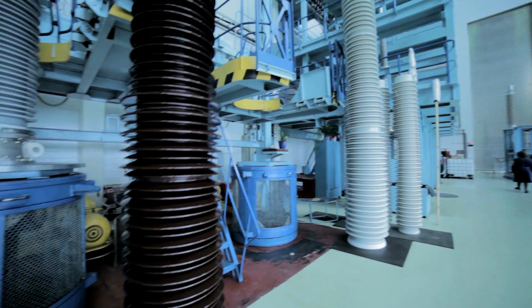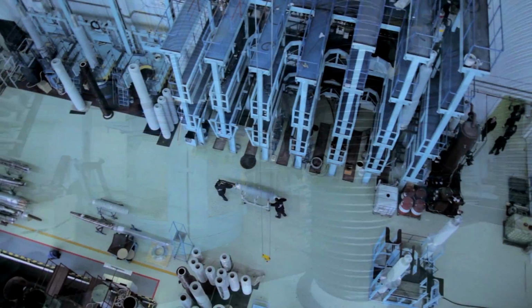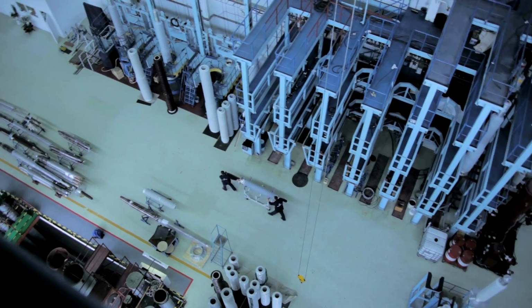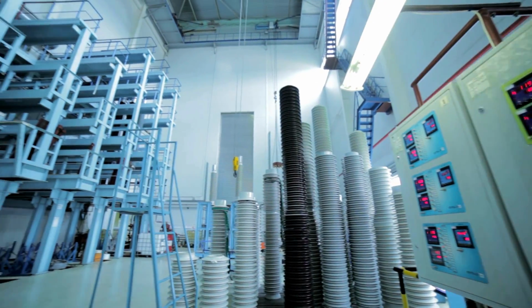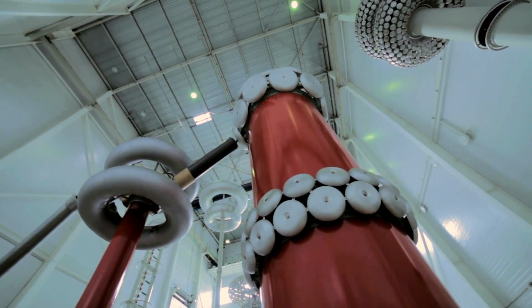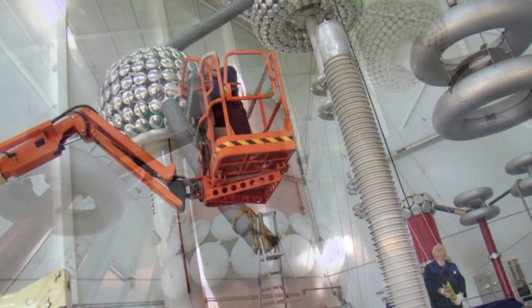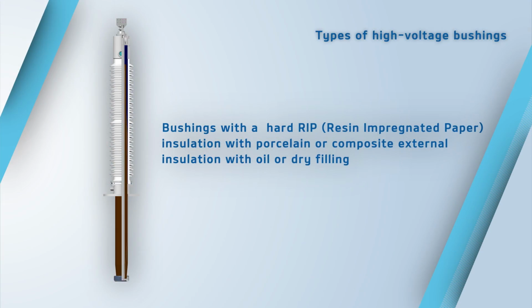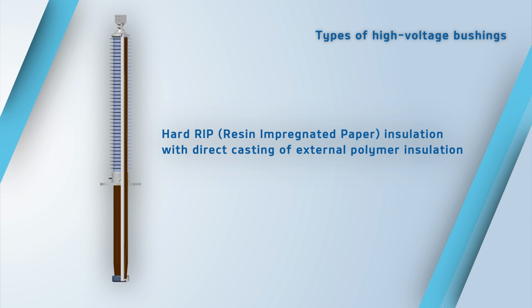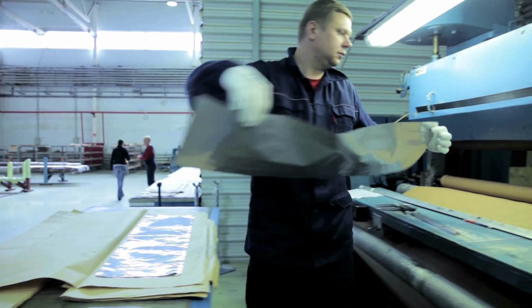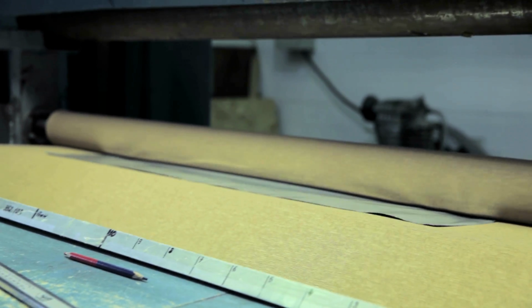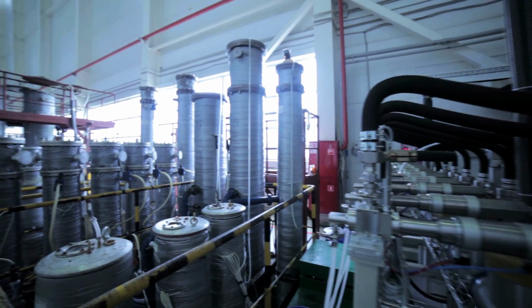High-voltage bushing is an important transformer component that ensures its reliable, fault-free and endurable operation. Internal insulation is a key construction part of a high-voltage bushing that defines its technical and operational features. Presently, the most advanced type of internal insulation is a solid RIP insulation. Bushings with this type of insulation are highly reliable and more durable thanks to low dielectric loss and partial discharge level in the insulation, its thermal resistance.